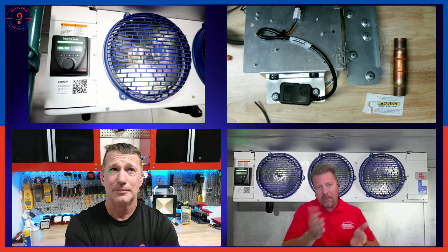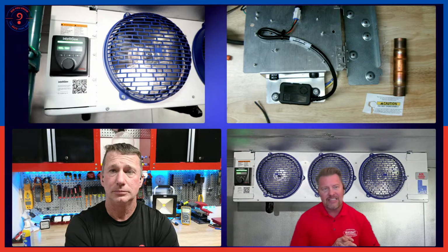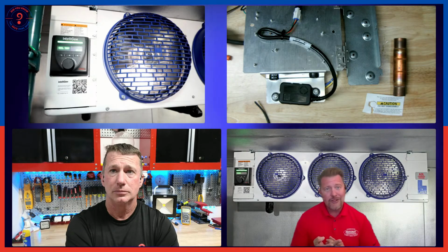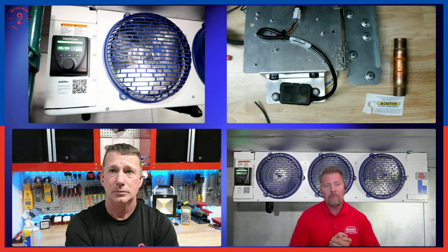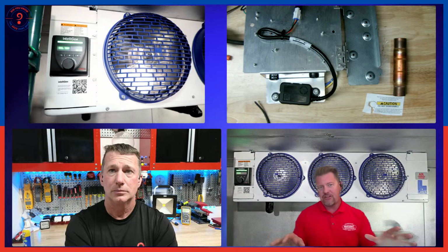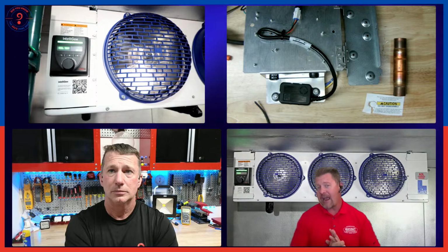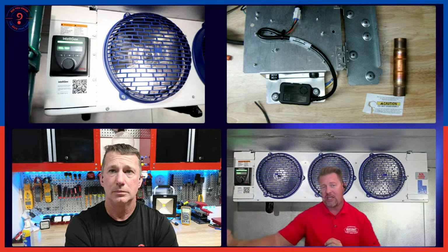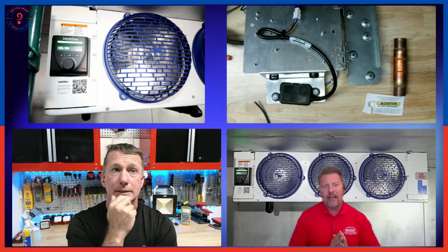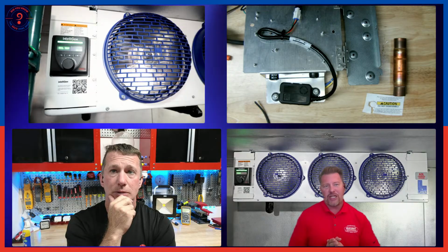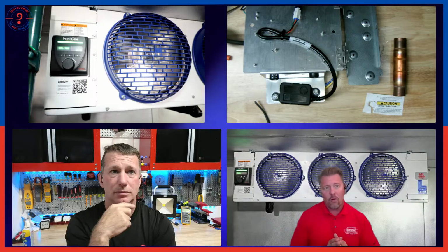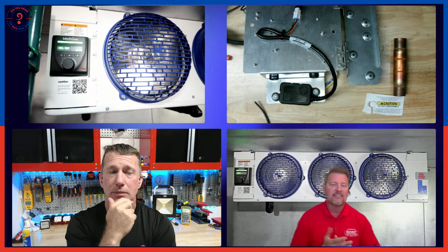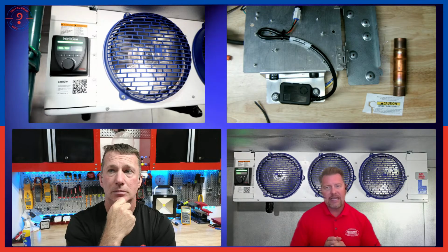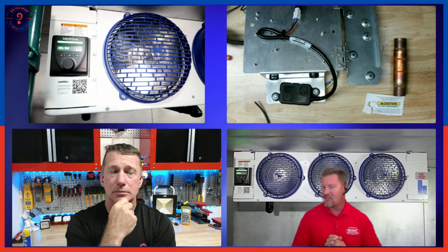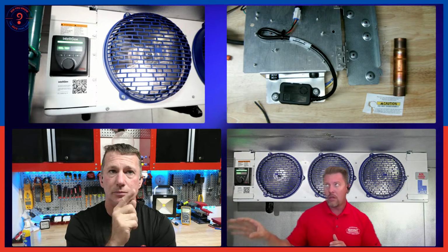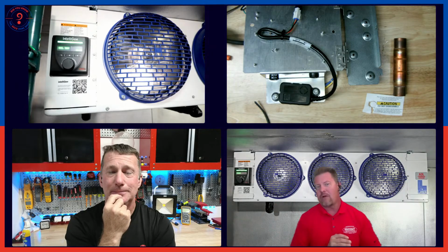It's a great feature. But for the A2L conversion, what's great about this is we didn't have to change the expansion valve. We didn't have to change a nozzle. All we had to do was, when we do go from an A1 to an A2L, one thing that we do have to do with Intelligen is we have to factory reset the control board. We can't just change to an A2L refrigerant. Oh, I got you. It does require a factory reset. Now, for a traditional A1 system, to go from 448 to 404 just requires turning the knob and selecting a different gas. Okay. To go to an A2L, we do have to factory reset. I haven't talked to the engineers to find out why that's required. I think because it has to look for the RDS kit at that point. I believe that's why the factory reset is required.